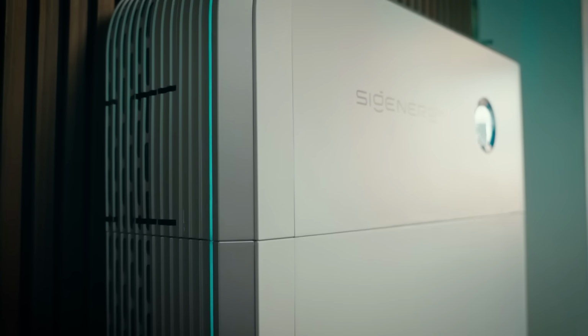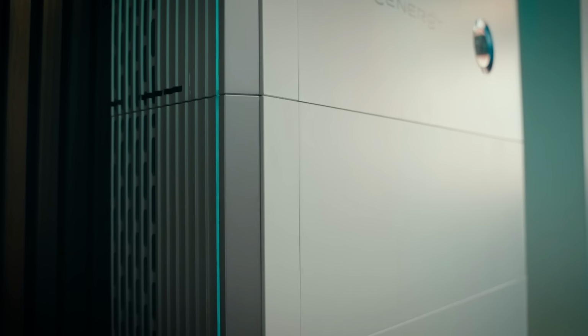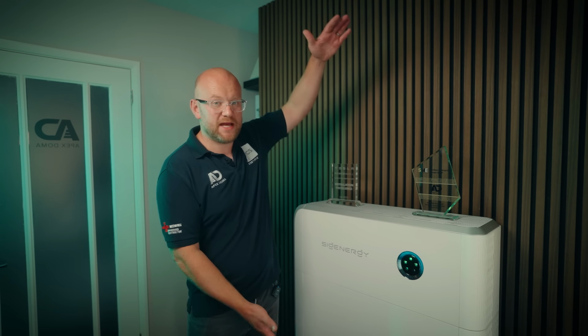Now talking of battery packs, we've got a few different sizes. There's a 5 kWh version being phased out for a new 6 kWh version, and 8 kWh versions being phased out slowly for the brand new 10 kWh versions. The one thing on the 10 kWh versions is they're actually a 9 kWh battery - it's kind of done for marketing purposes, just a little side note since I found that a bit confusing personally. But these are interchangeable with each other as well, so you can put a 5 with an 8, or a 6 with a 10, and mix and match them. Each energy controller can have up to 6 battery modules.